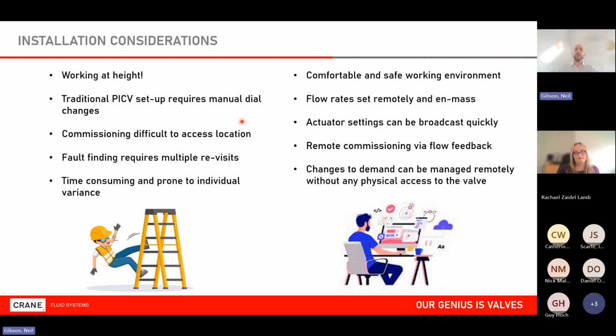So we can remove that issue, the number of revisits, and this time-consuming process of setting up dials, going to each valve, etc. I can now work comfortably from a safe environment. Flow rates can be set not only remotely but en masse. I can change actuator settings. Another example of that is the actuators come as default direct acting. Quite often people will want to change that to reverse.